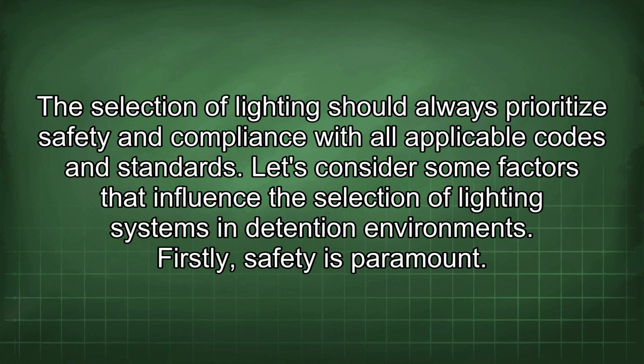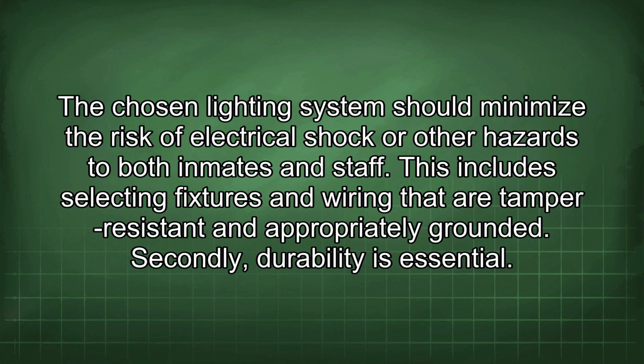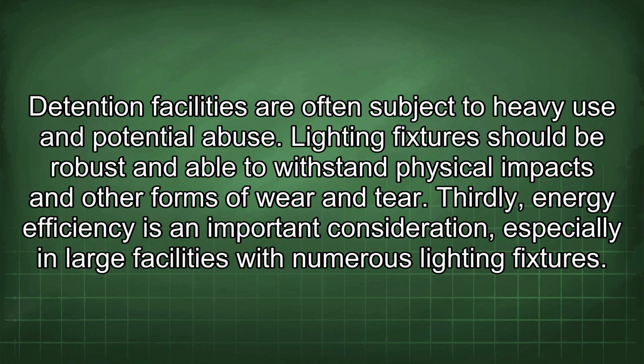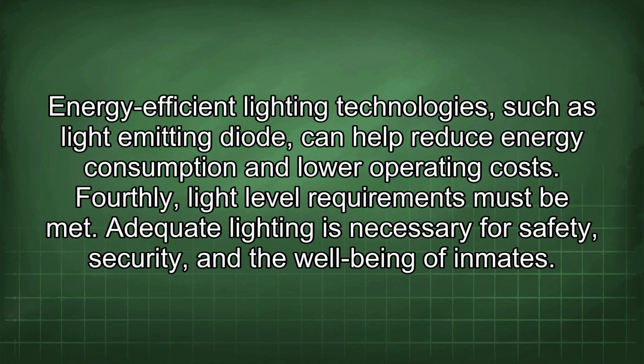Let's consider some factors that influence the selection of lighting systems in detention environments. Firstly, safety is paramount. A chosen lighting system should minimize the risk of electrical shock or other hazards to both inmates and staff. This includes selecting fixtures and wiring that are tamper-resistant and appropriately grounded. Secondly, durability is essential. Detention facilities are often subject to heavy use and potential abuse. Lighting fixtures should be robust and able to withstand physical impacts and other forms of wear and tear. Thirdly, energy efficiency is an important consideration, especially in large facilities with numerous lighting fixtures. Energy-efficient lighting technologies, such as light-emitting diode, can help reduce energy consumption and lower operating costs.